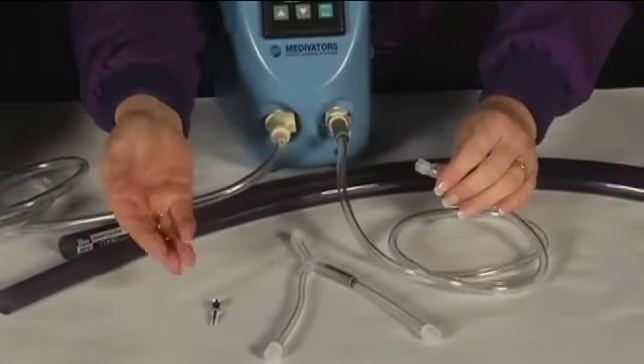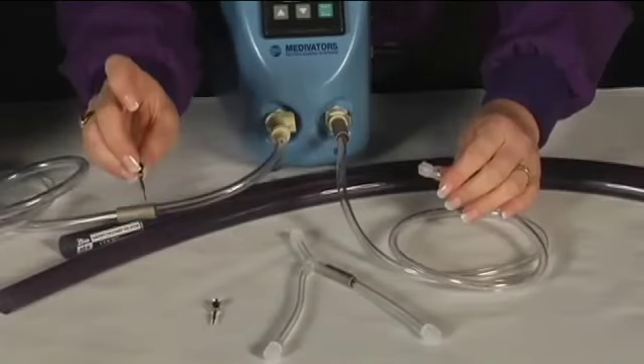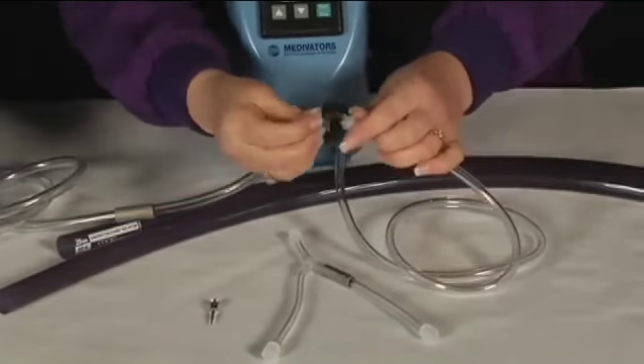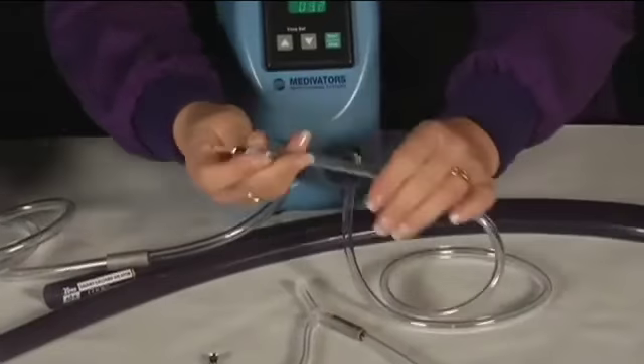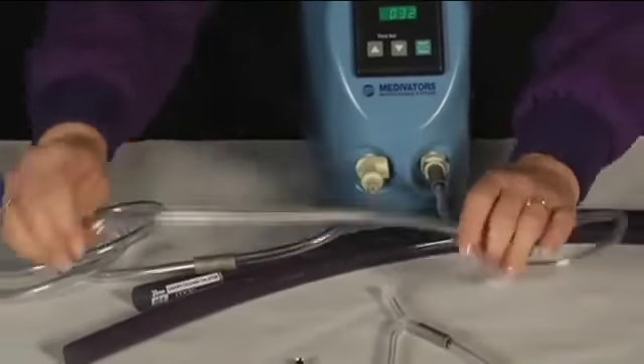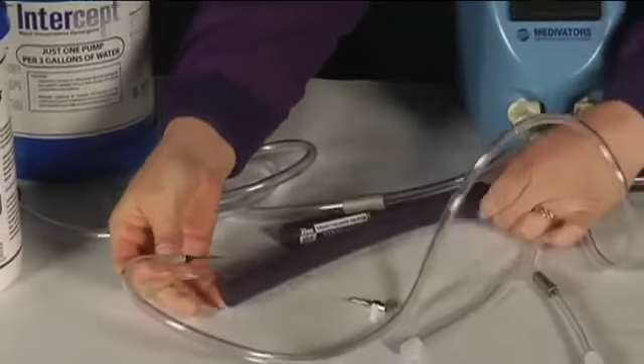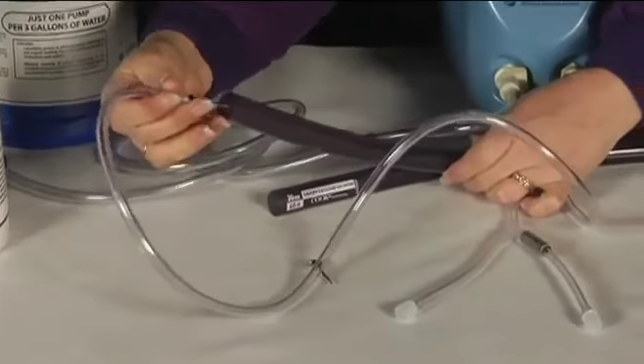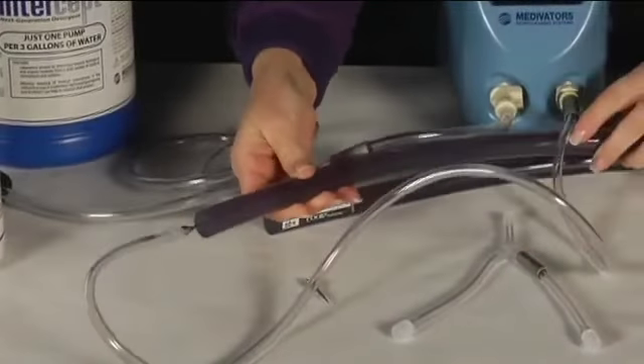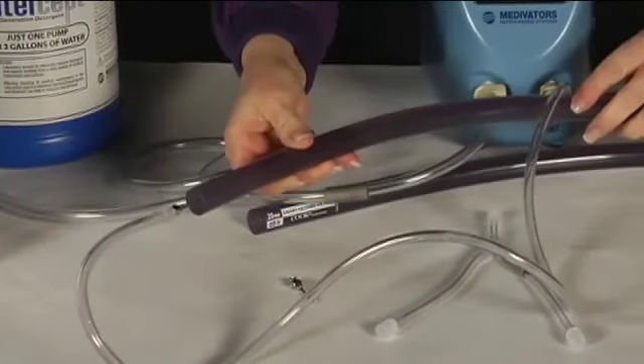Attach the manufacturer-supplied flushing adapter to the universal cleaning adapter extension line. Push the dilator onto the end of the flushing adapter. Refer to the Scope Buddy rinse matrix to obtain the required flushing time, set the timer on Scope Buddy, and flush dilators according to Section 9, Operation Instructions.